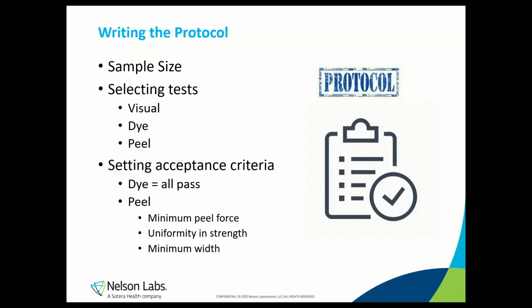For seal strength, the preferred method is peel testing to determine the peel force required to open a section of the seal. Peel is preferred over burst because it's testing a uniform coupon that can be directly compared to other peel data. We can also test multiple locations on the sealer to ensure there is an even seal strength. This might include pulling multiple coupons from a long seal on a large package, or sealing packages at the left, center, and right ends of the sealing bar, and then cutting a coupon from each small pouch to see if the strength is the same.